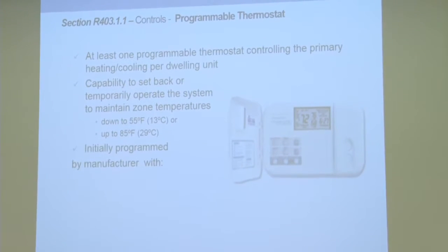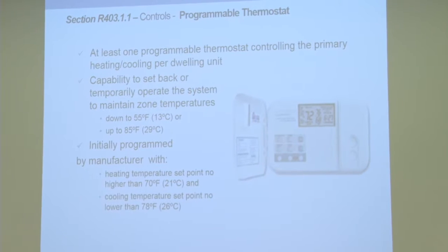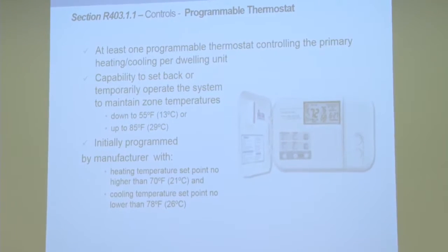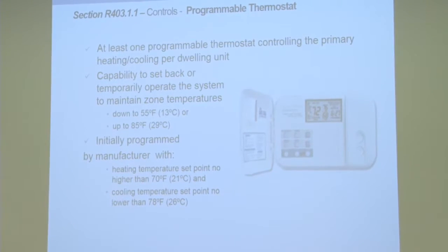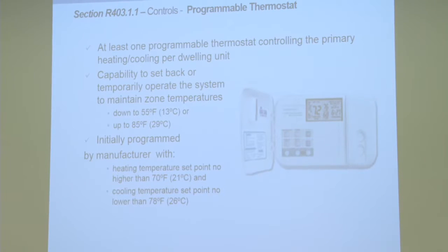So thermostats. I'm going to be completely candid with you. I never did a final inspection where I went and verified that the thermostat was programmed per the requirements in the code, or verified that the factory setting was 70 and 78. That's what the requirement says. I think everybody's building thermostats to that.